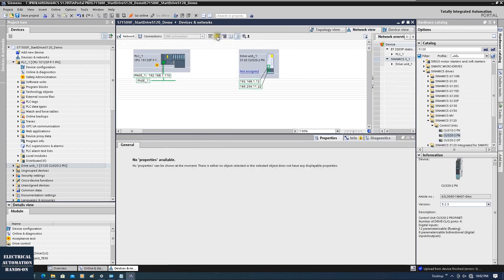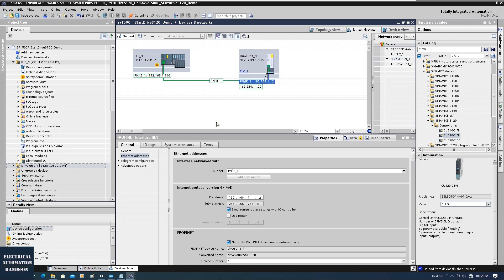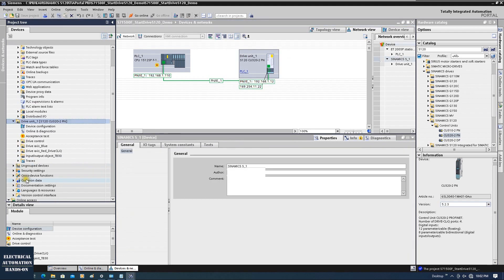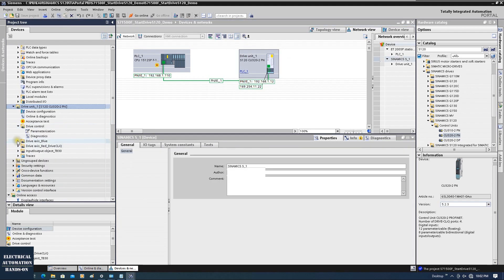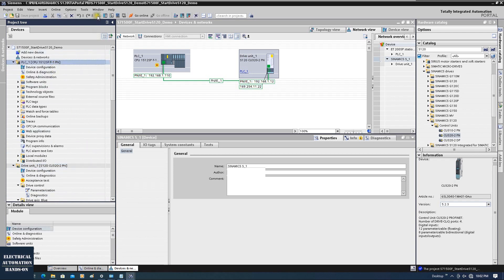Let's shift to the Network View. Click the small eye icon to see the IP addresses. My CPU IP address is 192.168.1.110, and this drive is 192.168.1.12. Click this PROFINET port and drag it to the CPU PLC controller to set up this connection. We can see the PROFINET device name is the same as this station name. If we expand, we can double-check all the hardware configuration — we can see the drive and the axis. We uploaded all the hardware configuration.